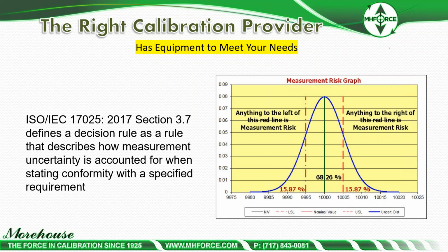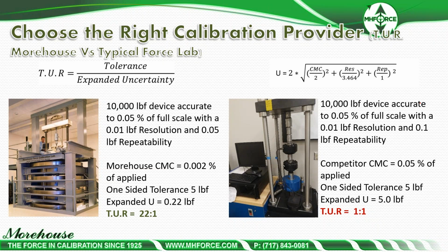Right calibration provider, the end of it. Hey, it's simple. Has equipment to meet your needs. There, decision rule. How measurement uncertainty is going to be accounted for. This is the graph. Lots of people have seen it. Anything to the right of the red line is measurement risk. In this situation, we have very, very high measurement risk. This actually came from aircraft scale with a very coarse resolution and a very tight accuracy. And no matter what you did, unless you hit nominal, you had to hit nominal with a dead weight machine or you were going to be out of tolerance.